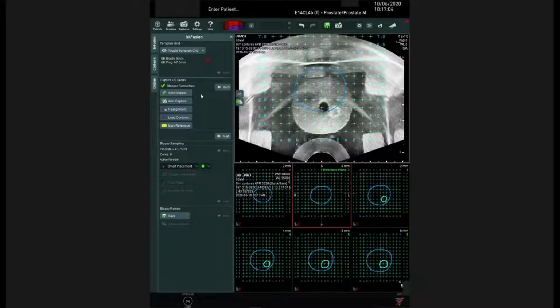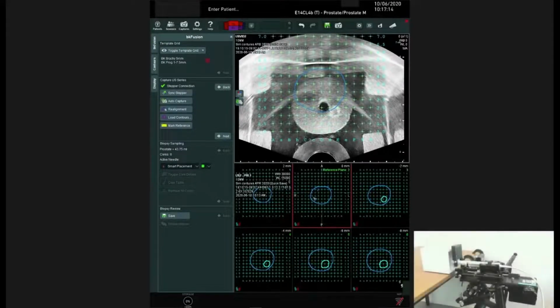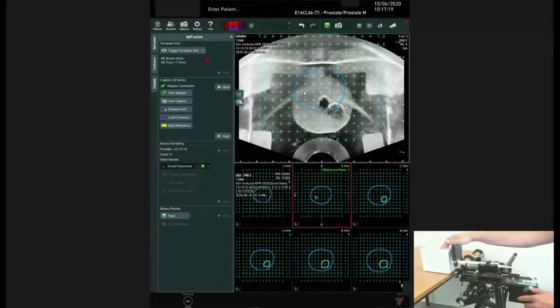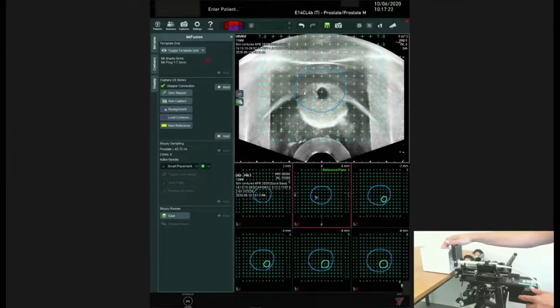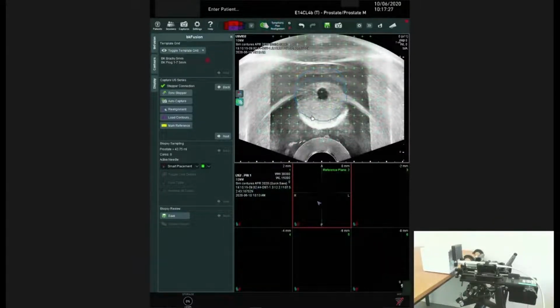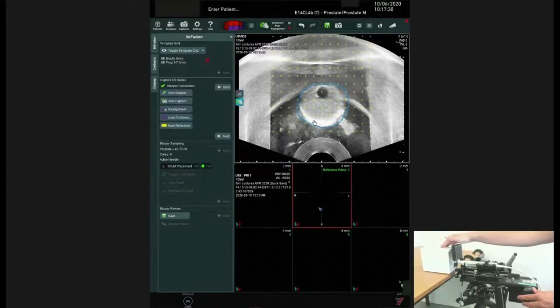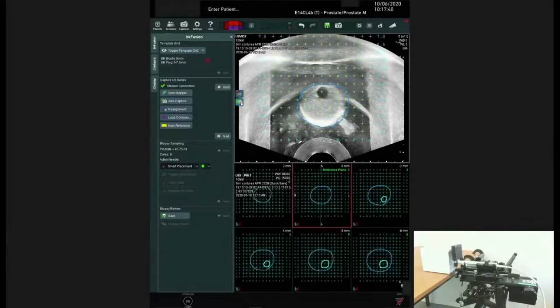Next, on the ultrasound image, find the reference plane that matches the MR contours. This is done by stepping the transducer into the patient until a good match is found. Then move the MRI contour until there is a good match, like you see here. When you are satisfied that they are aligned, click on Sync Stepper.